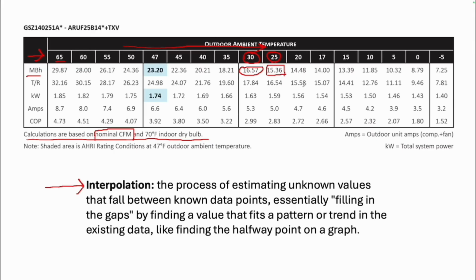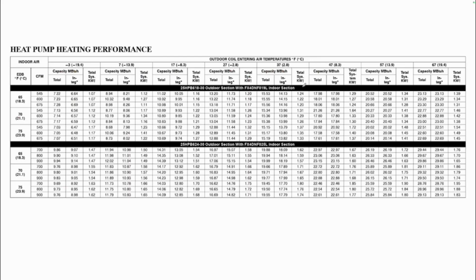And now that I know how many BTUs the system is moving, let me show you what the manufacturer says it should be doing. Being able to show them on paper that the system's performing, or maybe you uncover that the system's not performing, and at least you can address it then. Either way, it's going to help you either instill confidence, or it's going to help you understand what needs to be corrected on the system.